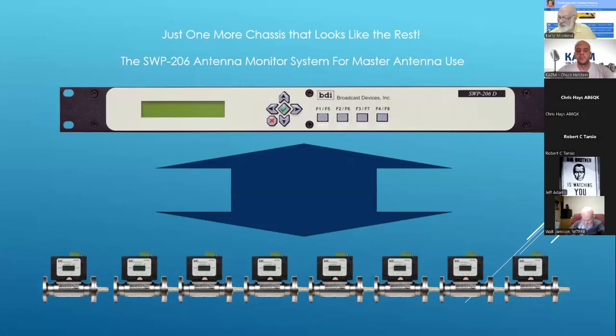What this box does is it manages the interlocks in such a way as I just described. If you have a master fault, which would affect all of the stations, it'll issue an interlock open to all stations. If you have a fault with one station, or there's an interlock event that would cause that station to go off, like a lockout tagout switch being thrown or something like that, then only that station would go off. So it's managed interlocks. And power meters connect directly to this with a Cat5 cable, and we basically do everything with Cat5 cables these days. We don't do too much with crimping tools and that kind of thing anymore.